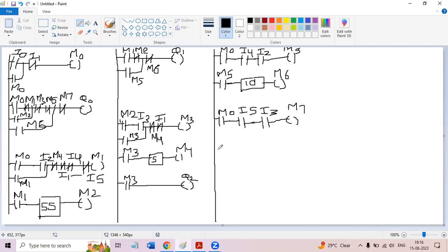And it will start this valve. So here, this valve will start from M7, and a timer will run for 10 seconds. So from M7, run a timer. See, we can work on this timer also, but why complicate? Better we take a new timer. There is no problem, we can take many timers. After 10 seconds, M8 will come and M8 will again start the conveyor.